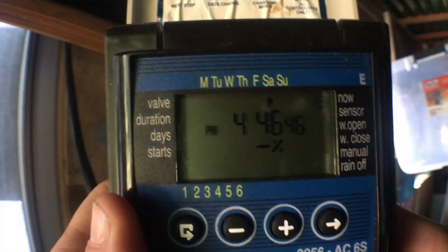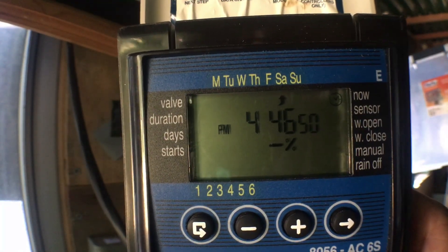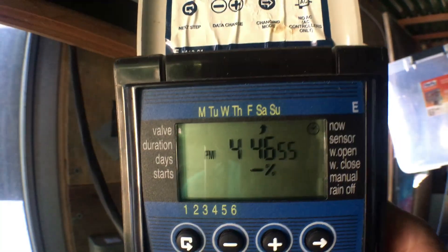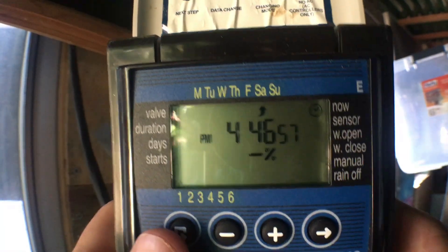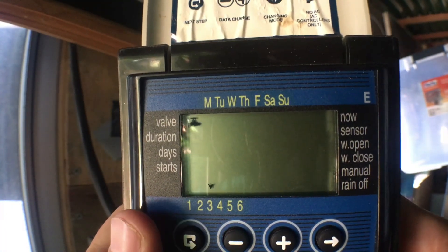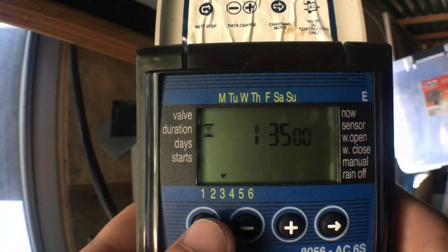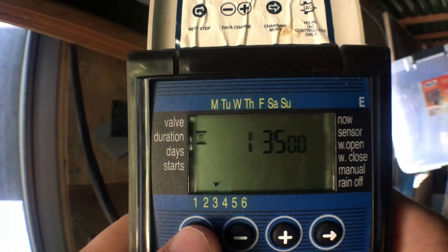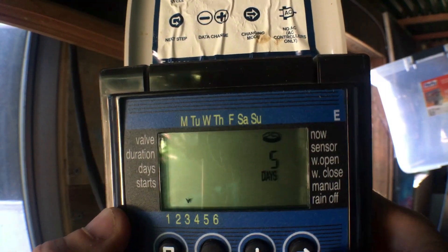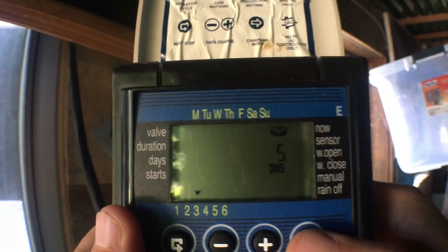Now let's look at how to set something for a non-cyclic irrigation cycle — specifically how to take something already on a cyclic cycle and set it to specific days of the week, because it can get a little confusing. I'm going to select valve three, which is feeding perennial fruit trees. Duration is one hour 35 minutes — I'm happy with that. Moving to the next menu: Days. Right now it's on cyclic irrigation, every five days, for one hour 35 minutes. I want to change that.